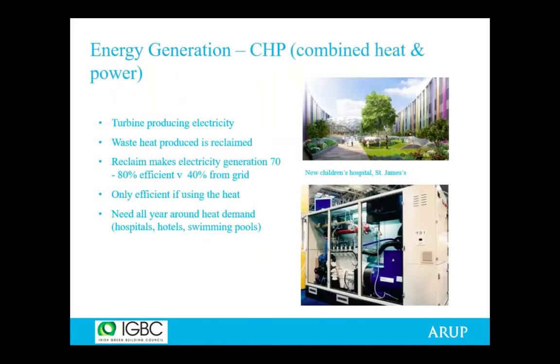Combined heat and power isn't actually a renewable technology in that it's not free energy, but it is a very efficient technology, so it's considered a renewable under the building regulations. A combined heat and power plant in Ireland would generally be powered by natural gas, which drives a turbine to produce electricity, and the waste heat from that electricity production is captured and used in a building for heating or hot water. So it's the reclaiming of the heat that makes it considered a renewable technology.